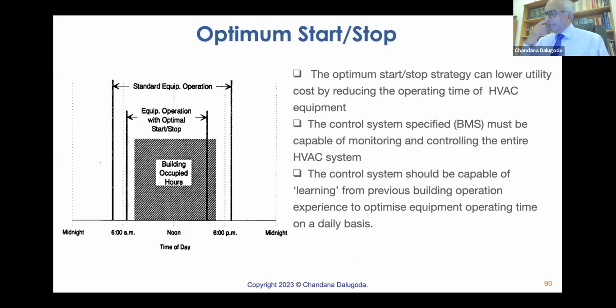the BMS people have done there, a building operation usually 8 a.m. to 5 p.m. On Mondays, they start the chiller at 6 and maybe at 4:30 they stop. You would think it is a waste of energy. No, 6 to 8 unoccupied will absorb coolness into the building, pre-cooling. That will offset the load.